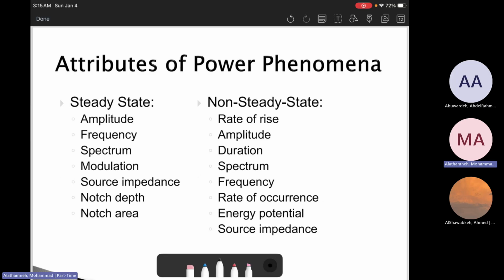So a lightning impulse can be extremely high amplitude but very short. So the key is rate of rise and peak, and the damage is insulation stress. A voltage sag may not damage insulation, but it can crash control systems. So the duration and depth really matter. This is why customers can report different problems from the same feeder. One customer has a motor, mostly tolerant, which is fine. Another has PLCs and variable frequency drives, which are very sensitive. Same network, but different equipment. One customer complains, the other does not.